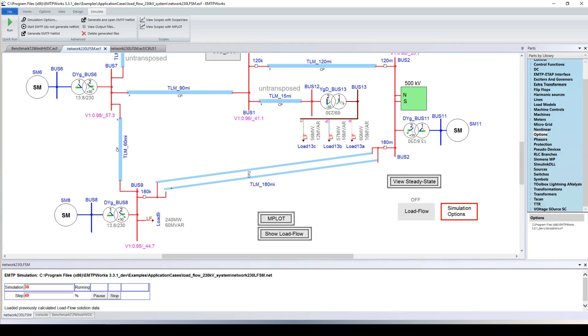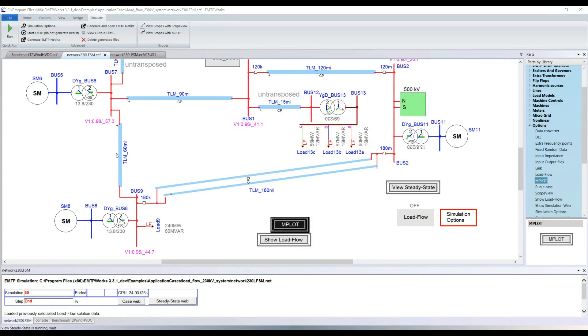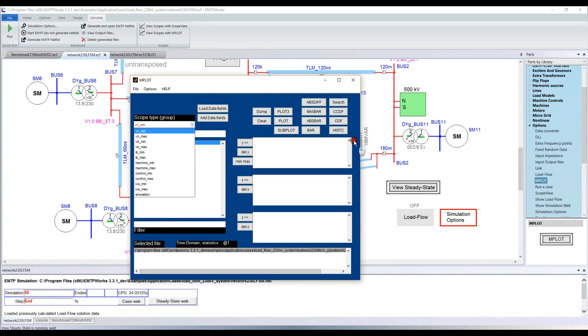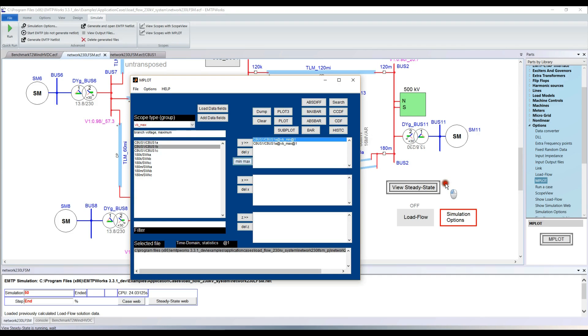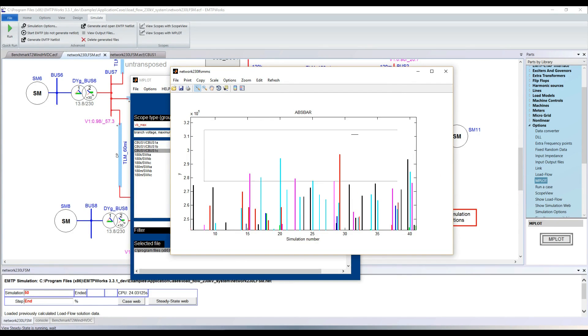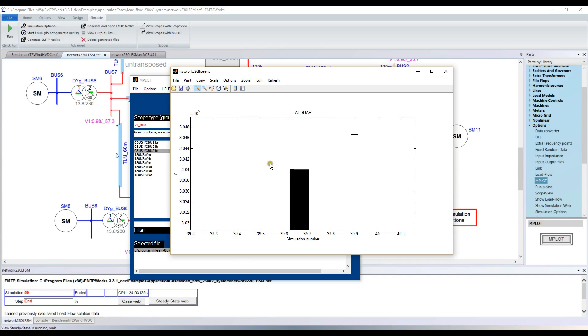After the 50 simulations complete, we use MPLOT — another tool similar to scope view for displaying waveforms — to look at the maximum and minimum for each simulation and identify the worst case. We display the absolute values of both maximum and minimum, since the worst case can be a negative value. Zooming to the top, we can find the highest overvoltage across all simulations.